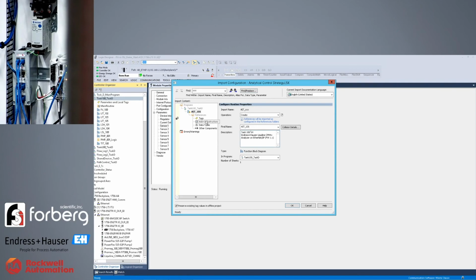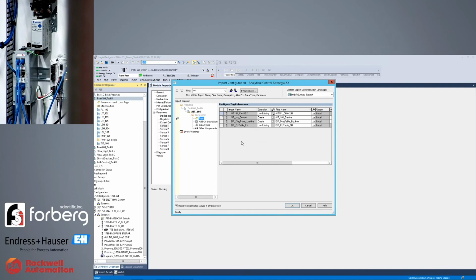When I come into the tags, one thing I'll point out is that it did pick up the name we gave it when we added it to the Ethernet I/O tree, so it's going to use that existing name. It's going to create a new instance called AIT 101 device, and I'll also add the description at the beginning so it knows it's for tank 100.